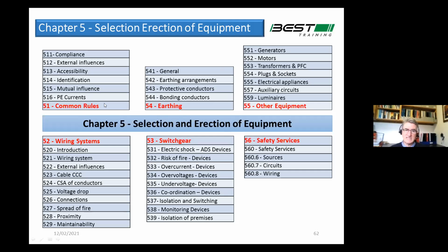So this is broken into 6 sections, and the first one is part 51, which deals with common rules. So things like color coding of cables, identification. It deals with PE currents, which is protective earth currents. These are normal currents in a healthy circuit that are flowing through the earth wire, and it makes an assessment of them to make sure you're not going to get nuisance tripping.